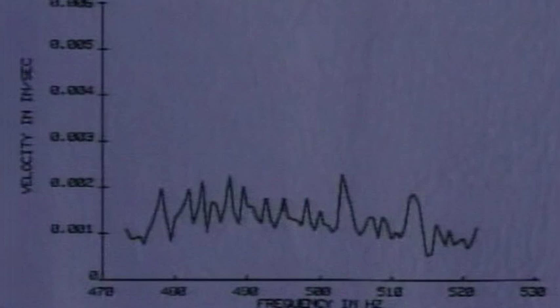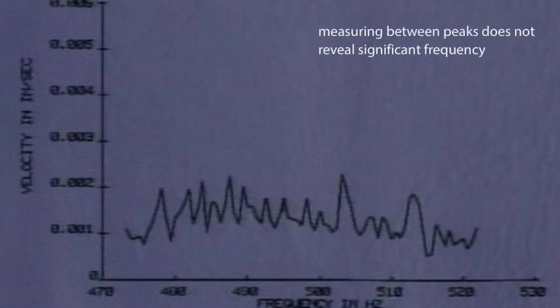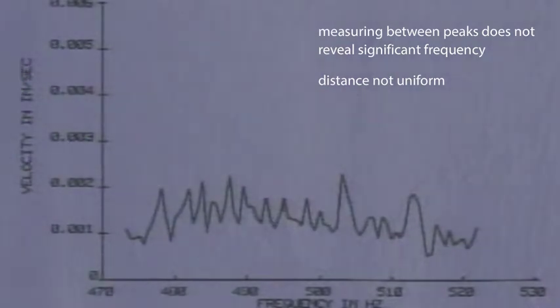Let's zoom in and look at the peaks more closely. They appear poorly formed and random. Measuring the distance between the peaks does not reveal a significant frequency, such as the one-times or vane-pass frequency. And the distance is not uniform between different pairs of peaks.